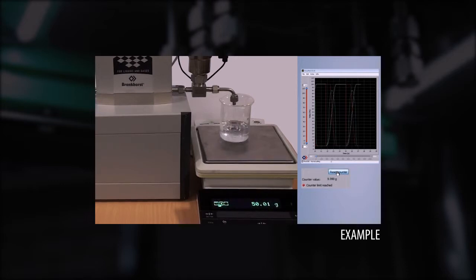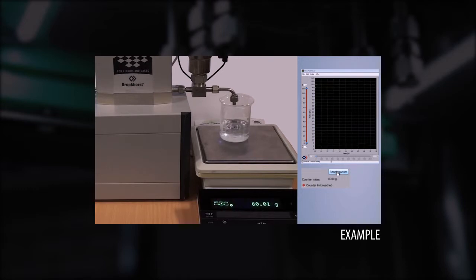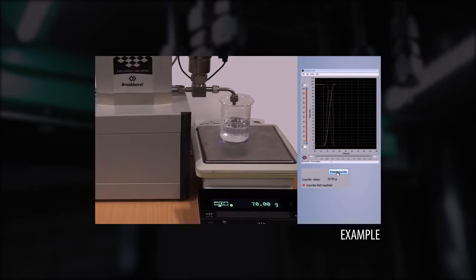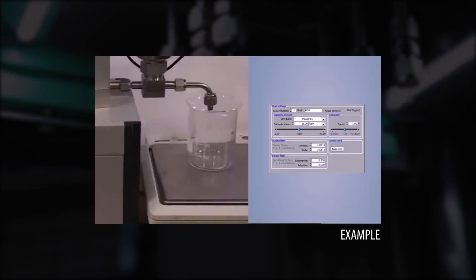The unit will dose true mass flow, independent of ambient temperature and back pressure. You can consider the mass flow controller as an inline weighing scale for flowing mass.